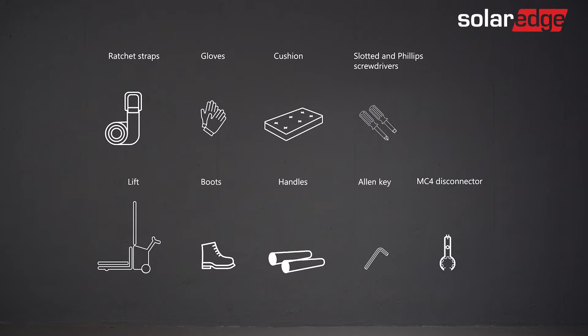The first step is to remove the battery from the inverter settings by using SetApp. Launch SetApp and scan the QR code on the inverter. Then, connect to the inverter by switching the on-off P switch on the inverter to the P state for 2 seconds.